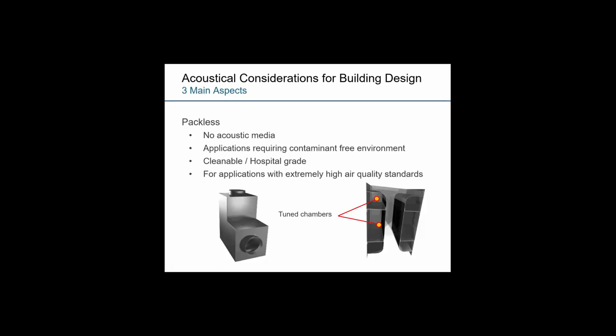Another example of a unique silencer that you may not be familiar with is a packless silencer, or these are also called reactive silencers. And these are a bit different in that they're typically completely made of metal. There's no acoustic media or material within the baffles. Rather, it's fabricated using tuned chambers that sound energy will propagate through and enter into these baffles and bounce around and be attenuated without transmitting through it as it would an empty duct type application. They can work very well for that intention, having tuned chambers to attenuate sound energy, and used a lot in applications with corrosion concerns or that need to be cleanable, or air quality standards require no absorptive material within them.